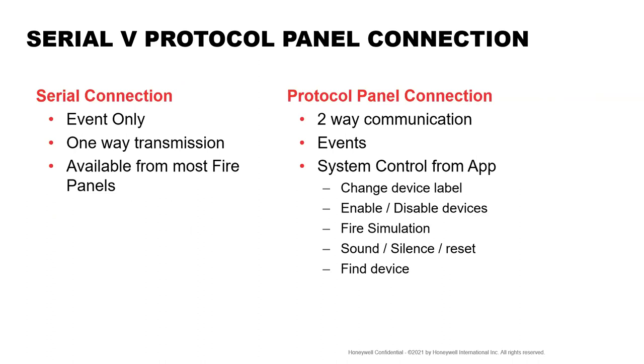So serial versus protocol panel connection. So serial connection, like through a 232, basically you're getting the event only. It's one way transmission. You can't send signals back into the panel. I don't know of a fire panel that's in the market at the moment that doesn't do it like this. Most, I'm not sure that all panels have printer ports on them anymore, but most of them would. That's where you'd get that information from. But as you can see, it's quite limited.